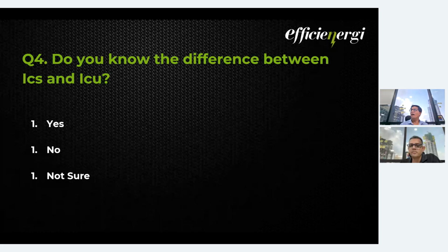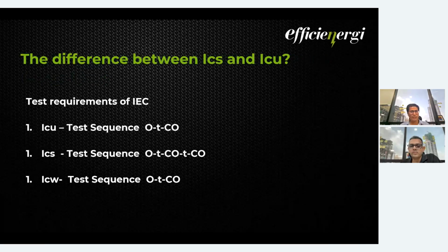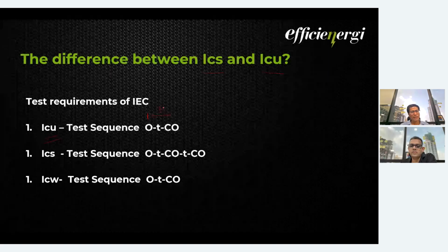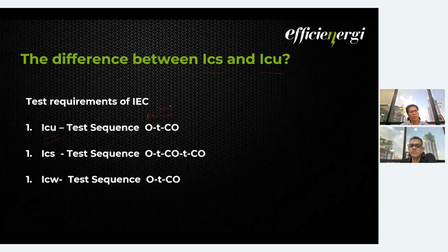So the difference I'll be telling in the next slide. The difference lies in, again, as I told you, ICS and ICU, which the manufacturer has to decide. There is no hard and fast rule. But the test requirement is this. For ICU, the test sequence is O-CO. O means the circuit breaker is in open condition. Then there is a time gap of not less than 3 minutes, and then there is one sequence of operation, close and open.